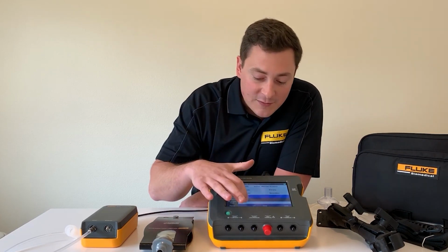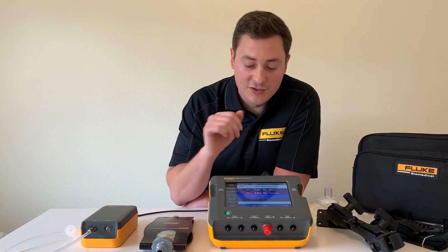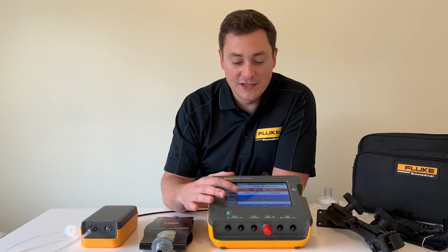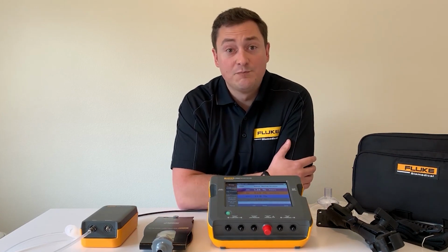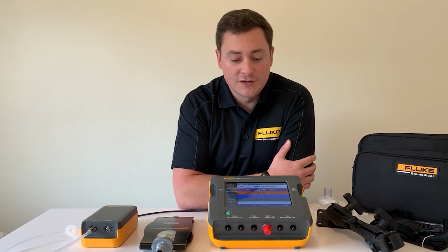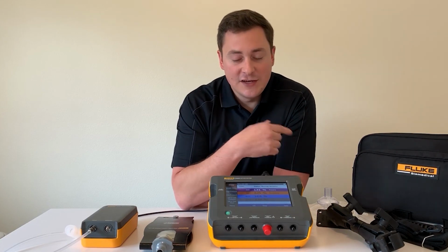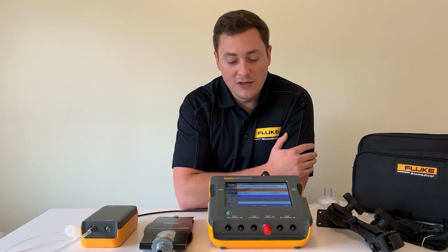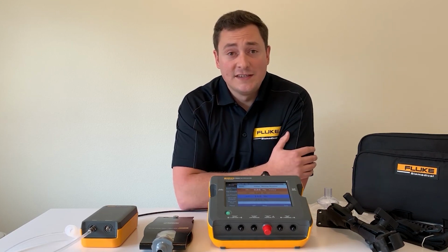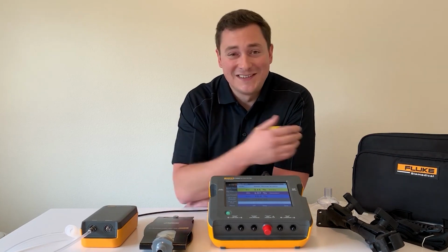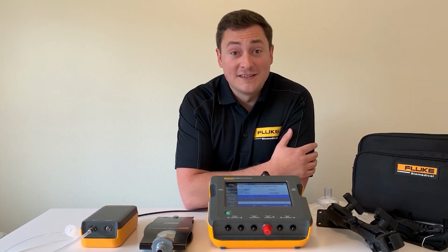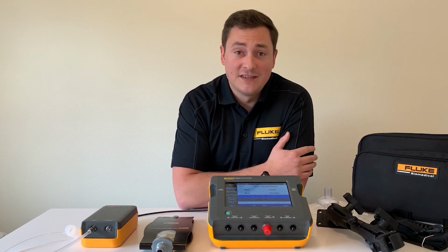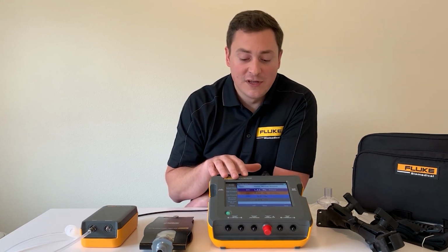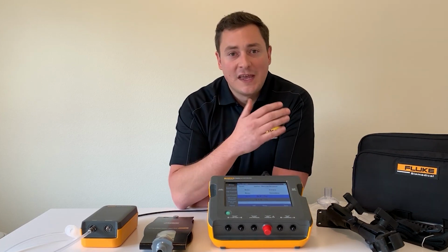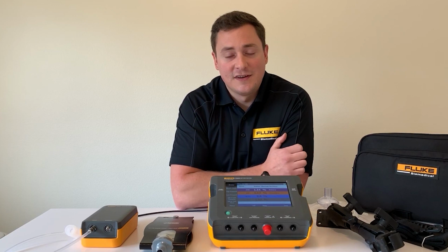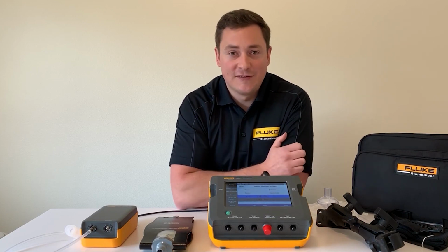So we're in warm-up accuracy, and I'm just going to throw it into demo mode to show you guys what this has. So N2O and CO2 are always there. Those are carrier gases, but they're overdosable. So we want to make sure those get measured. And then you'll see that the different agents come in. We measure all 5 agents, and we measure them automatically. So there's automatic agent ID. Vapor is going to tell you what it sees and not what you tell it to see. So there's no need to cycle power to switch agents. This is going to do everything for you. You'll also see that those colors pop up. So every agent that's identified will match with its international color code. So from a distance, you'll be able to see if everything checks out.